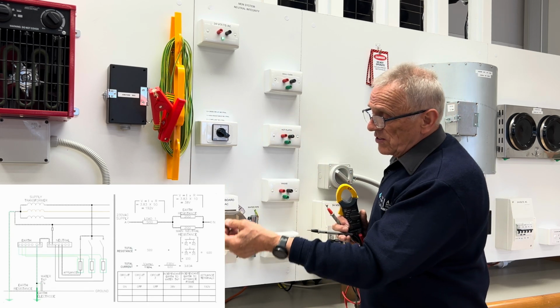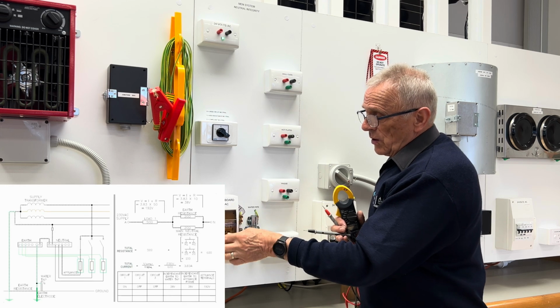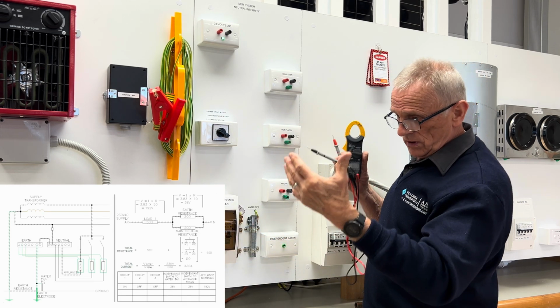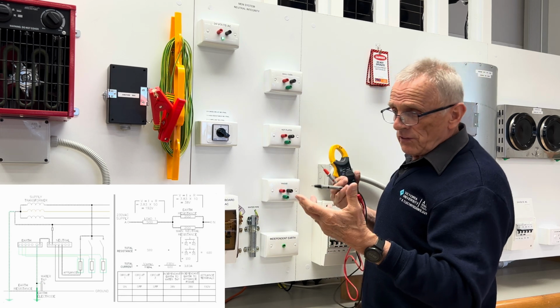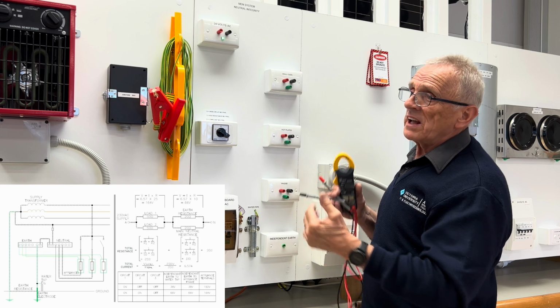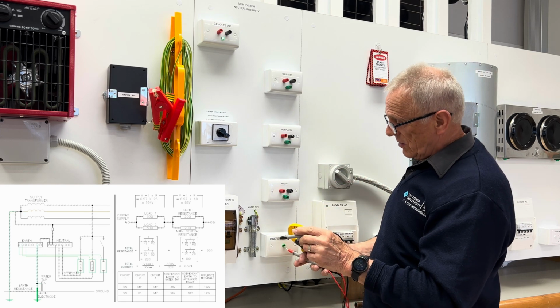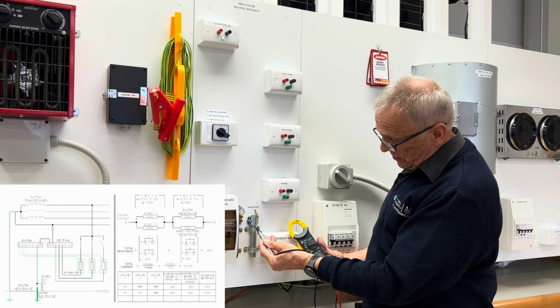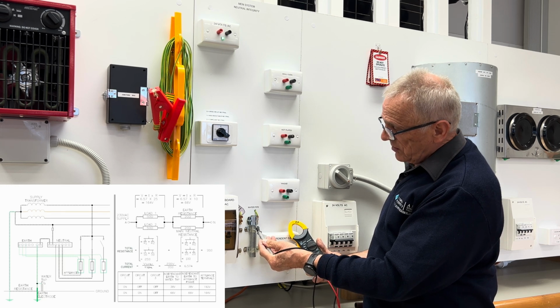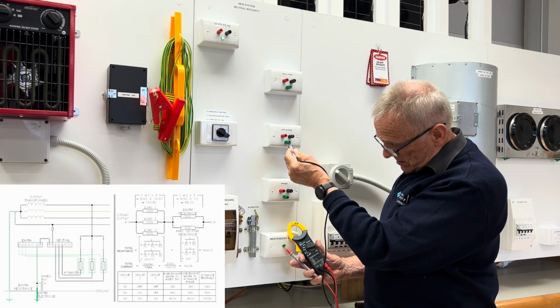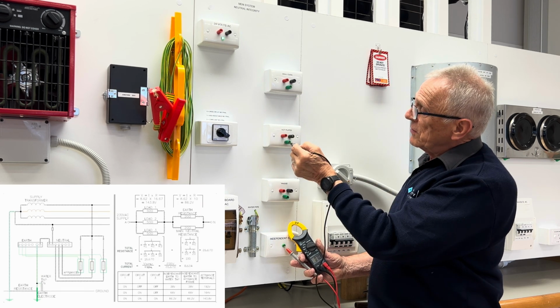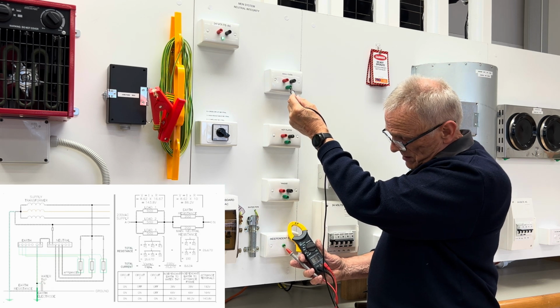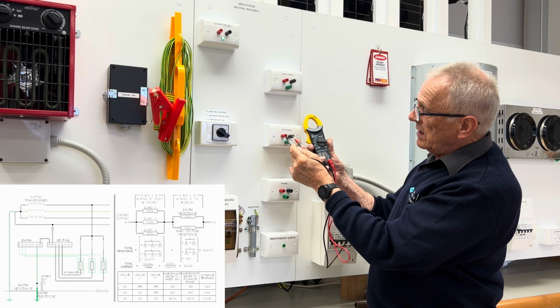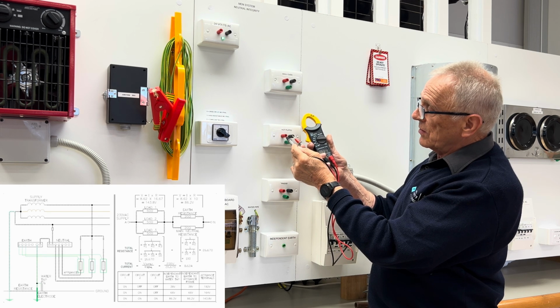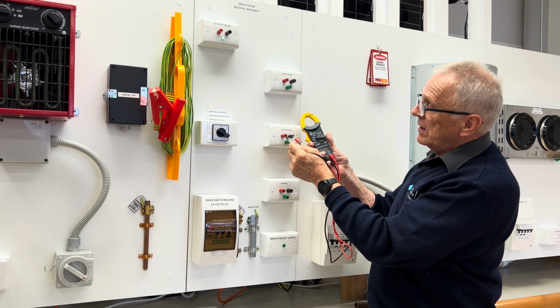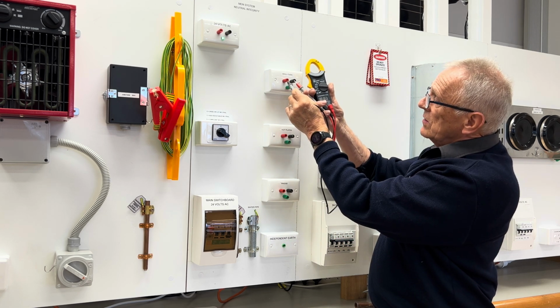Now, as we put loads on, we're actually dropping the resistance of the overall installation load. Therefore, the voltage drop increases on the earthing system and decreases again across the loads. You'll see here the voltage on the earthing system is up to 7.6 volts, and the same will be evident on the appliance hot plate, frame of the hot plate, and the frame of the wall oven. And across the actual hot plate, the load, we're at 17 volts, which could represent quite a voltage drop, you know, in an external situation, in a live situation.